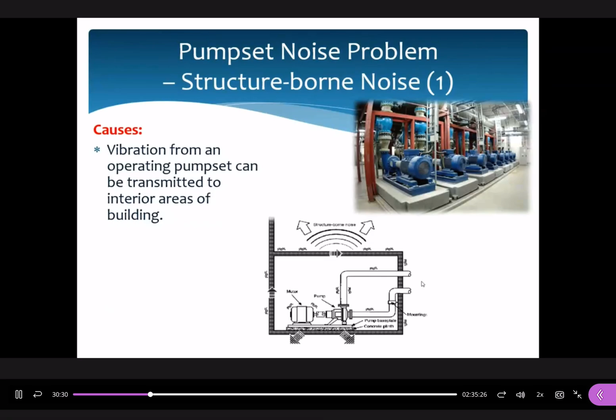The common approach: first, provide an inertia block. An inertia block is a kind of concrete pit - this is the concrete pit for supporting pump sets, and it helps add rigidity and stability to the pumping system. Second, below or underneath this inertia block, we still need to install vibration isolators. We need to combine these two approaches together, not only one, for lightweight structures it's okay to just install vibration isolators, but for heavy structures it's recommended to install both to support the whole system in a way that reduces the structural-borne noise effects.